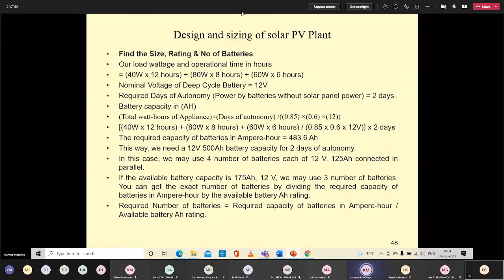So for the required days of autonomy, suppose I am selecting 2 days. The total watt hour of the appliances is divided by the battery efficiency you are considering, 0.85, multiplied by the DOD of 60%, and multiplied by the system voltage. So efficiency, depth of discharge, and system voltage will give you the ampere hour capacity for a 12 volt battery. Now, this is 483.6 ampere hour, but it is not available in the market.